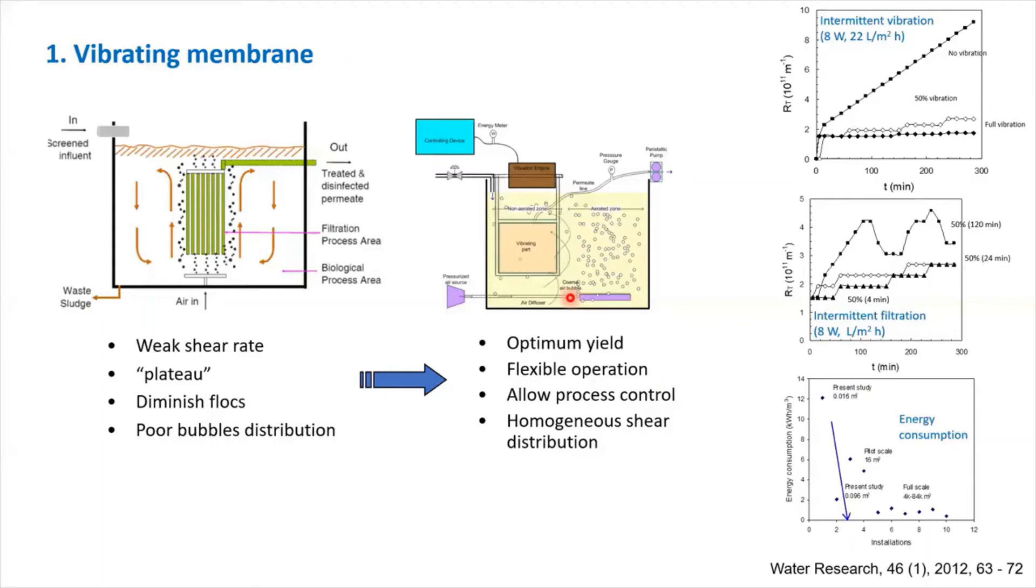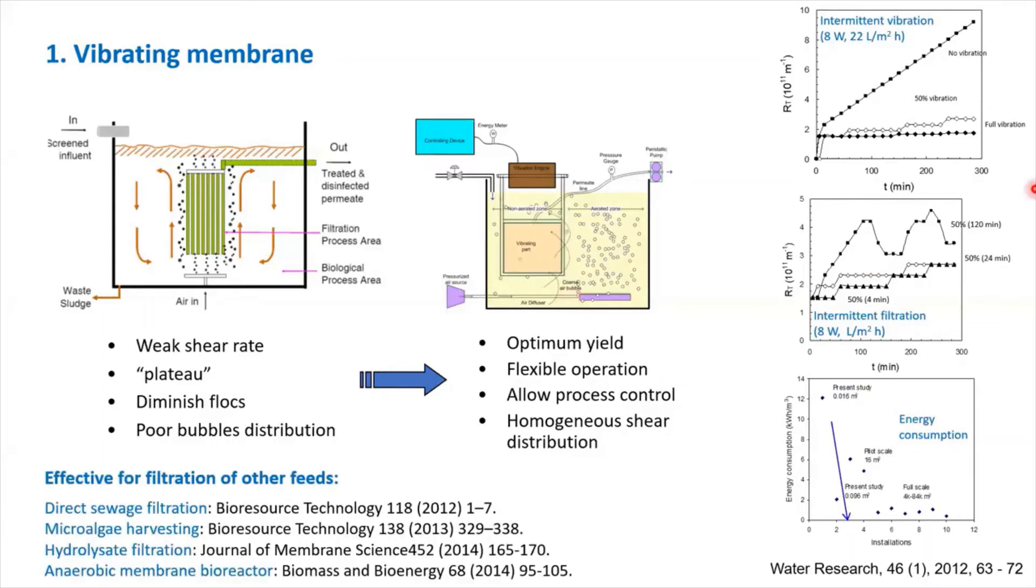We tested on membrane bioreactors, and we find out that the system is highly efficient. As you can see here, if you implement full vibration, you achieve almost no resistance, basically no pressure goes up here, compared to no vibration that continuously increases the resistance. It is highly efficient, the energy can be minimized if you operate it in intermittent operation. And we calculate the energy and the energy consumption is actually very low. The system is also applicable for a lot of different feeds, as you can see from a list of publications we have here.